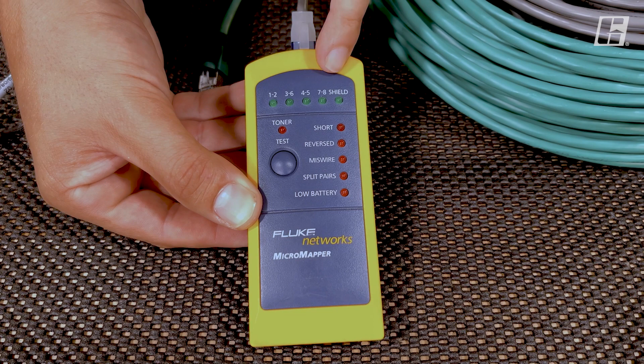We would see the same thing if any of the twisted pairs were broken, as well as all of these other conditions. Again, you'll have to consult your specific tool's manual to see, but this is a really fast way to verify network connections. Again, this is one of the most common failures that we see: someone making their own terminations and flip-flopping some wires, or even someone pulling on the cable too hard and breaking a wire internally.